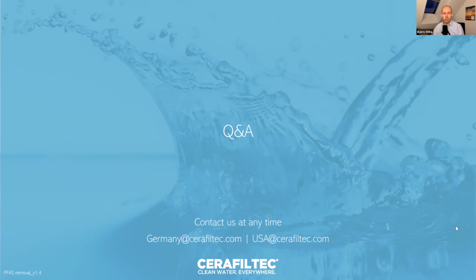How effective is it for short chain? We already talked about this, 99. What is the flux for the membrane? What flux are you running at Rome, for instance? Chris, maybe you can talk about Rome and then also the broader range that we typically target. In Rome, the target was 300 liters per square meter per hour, 300 LMH. In U.S. terms, take 58.8% of that, so probably closer to 160, 170 GFD.